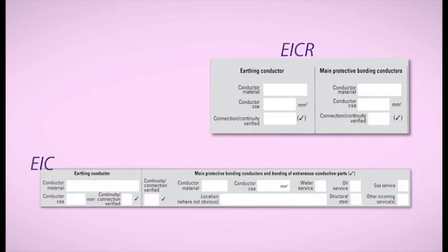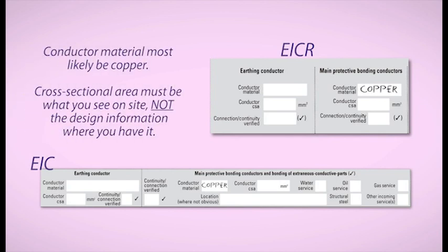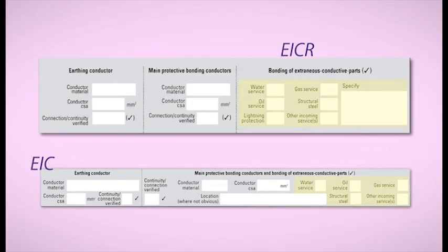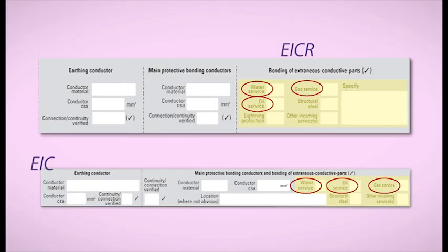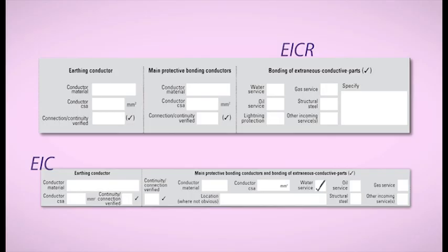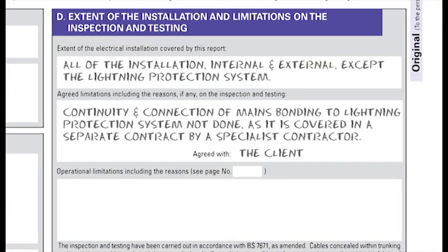Next, we have the main protective bonding conductors. Conductor material will most likely be copper, and the cross-section area must be what you actually see on site, not the design information where you have it. There are several tick boxes for the various extraneous conductive parts. For example, water, gas or oil. You would expect to see either a tick or an NA in each box, but for an EICR, you might also have a limitation or an outcome code referring to the urgency of the remedial action required, which we will discuss later. Any limitation you write must be fully detailed in the limitations box on the front of the EICR form.